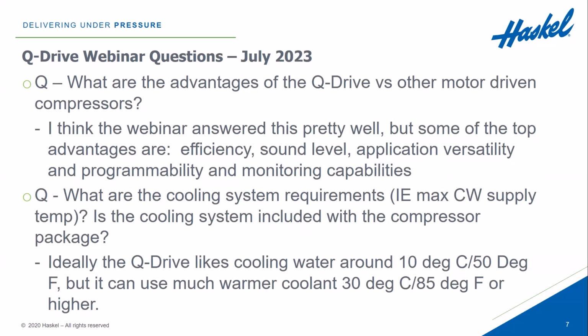What are the cooling system requirements? That is maximum cooling water supply temperature, and is that included with the Q drive? Ideally, the Q drive would like to see water or coolant around 10 degrees C or 50 degrees F, but it can be much warmer, as high as 30 degrees C, 33, 34, 35 degrees C, 85 or 90 degrees F, depending on your specific application. Normally, if we have warmer cooling water, we do need to have a higher flow of coolant through the Q drive to remove that heat that's generated.